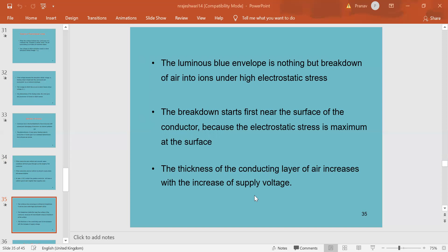And coming to the factors affecting corona. Some of the factors which affect corona are namely the atmosphere, conductors, line voltage, and spacing between the conductors. Coming to the atmosphere, in stormy weather conditions the number of ions in the atmosphere is more as compared to fair weather conditions. Hence, corona will occur in stormy weather at a much lower voltage compared with fair weather.